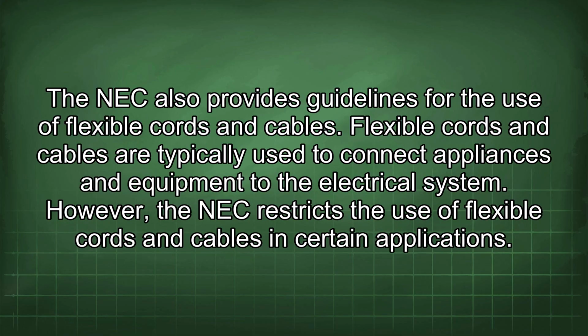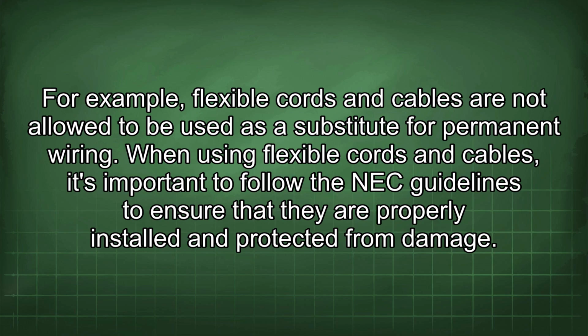The NEC also provides guidelines for the use of flexible cords and cables. Flexible cords and cables are typically used to connect appliances and equipment to the electrical system. However, the NEC restricts the use of flexible cords and cables in certain applications. For example, flexible cords and cables are not allowed to be used as a substitute for permanent wiring. When using flexible cords and cables, it's important to follow the NEC guidelines to ensure that they are properly installed and protected from damage.